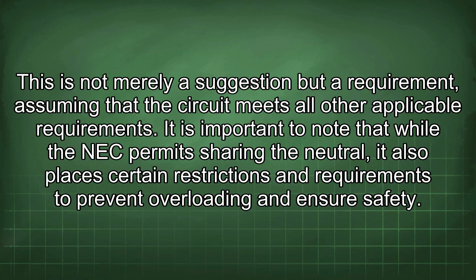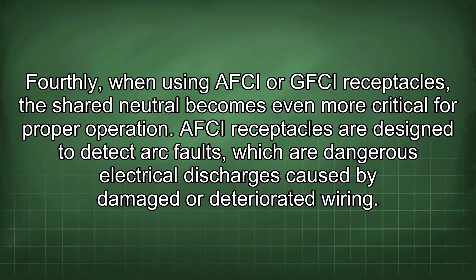Fourthly, when using AFCI or GFCI receptacles, the shared neutral becomes even more critical for proper operation. AFCI receptacles are designed to detect arc faults, which are dangerous electrical discharges caused by damaged or deteriorated wiring. GFCI receptacles, on the other hand, are designed to detect ground faults, which occur when current leaks to ground through an unintended path. Both types of receptacles rely on monitoring the current balance between the ungrounded and grounded conductors.